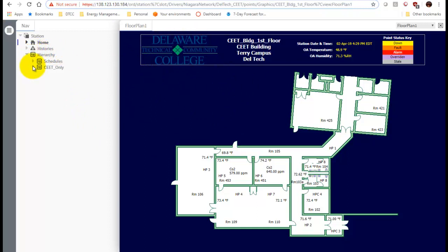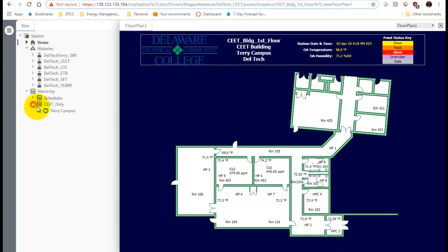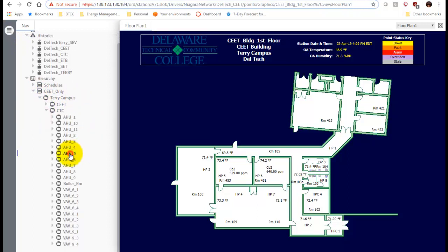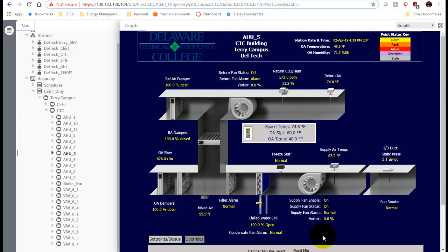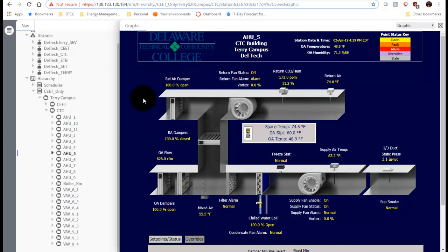We're logged into our BAS. Let's first look at air handling unit 5 just to get an idea of what's going on. If we look at the graphics, AHU5 is a VAV air handler that serves three VAV boxes. It does have outside air control and is controlled with inlet vane dampers - the vortex percentage is how those dampers are controlled. There's a duct static pressure and a chilled water coil to keep the supply air temperature constant.